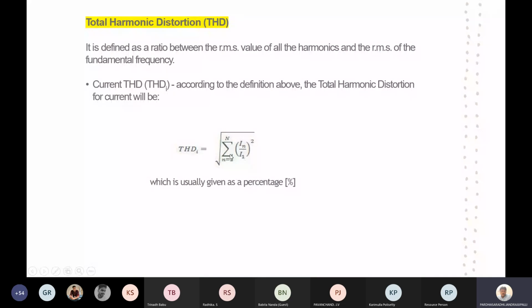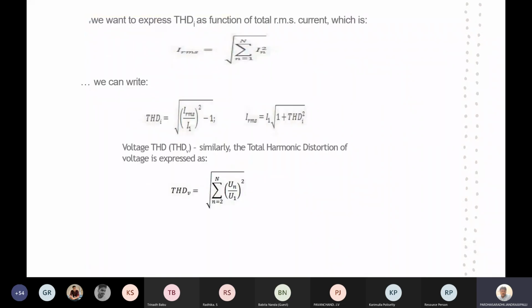Since the fundamental frequency is not part of the harmonics, it is not considered, and the sum starts from second order. Whereas the RMS value is sigma n equal to 1 to n of In square, and total harmonics can be defined in terms of IRMS to fundamental. So THD is equal to square root of (IRMS by I1) whole square minus 1, and IRMS is equal to I1 into square root of 1 plus THD square.